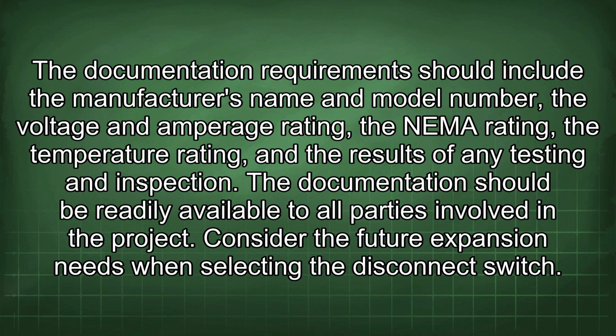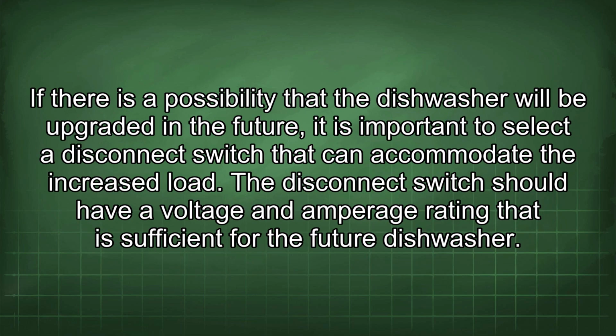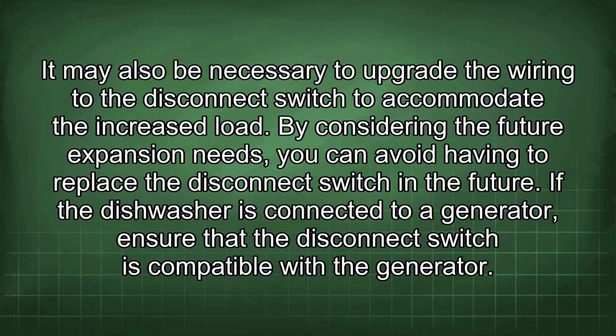Consider the future expansion needs when selecting the disconnect switch. If there is a possibility that the dishwasher will be upgraded in the future, it is important to select a disconnect switch that can accommodate the increased load. The disconnect switch should have a voltage and amperage rating that is sufficient for the future dishwasher. It may also be necessary to upgrade the wiring to the disconnect switch to accommodate the increased load. By considering the future expansion needs, you can avoid having to replace the disconnect switch in the future.